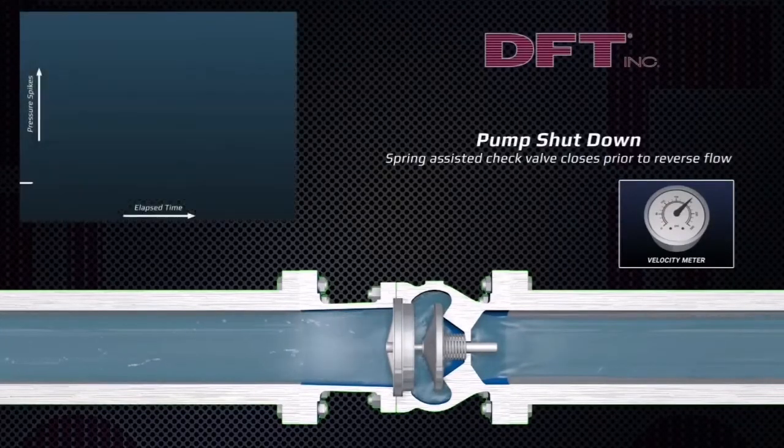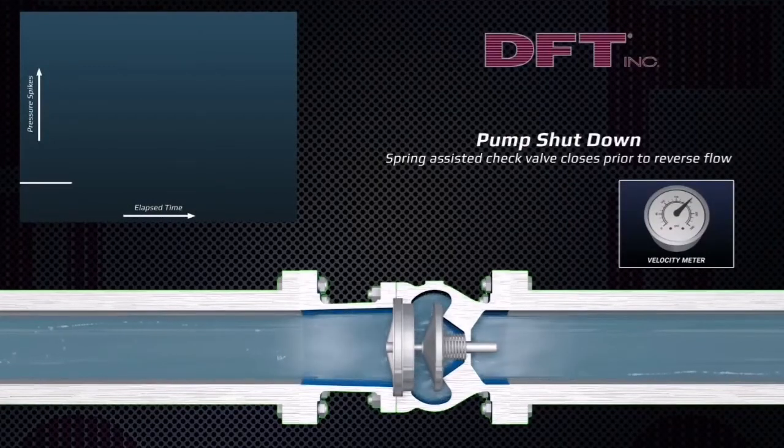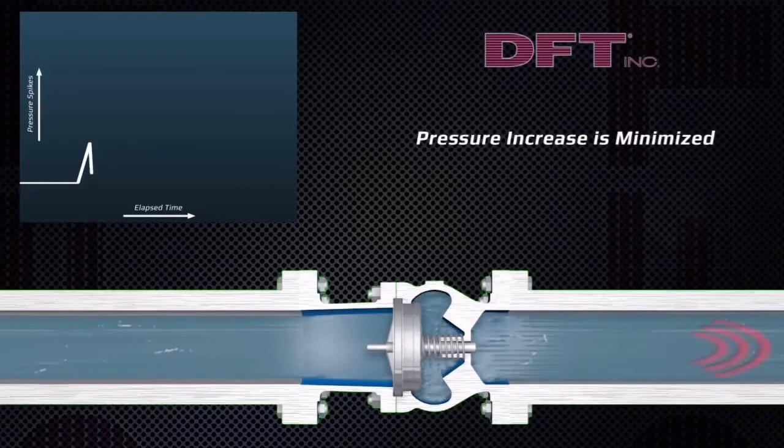When the pump shuts down, the spring-assisted silent check valve closes ahead of reverse flow before fluid momentum changes direction, thereby significantly reducing water hammer.